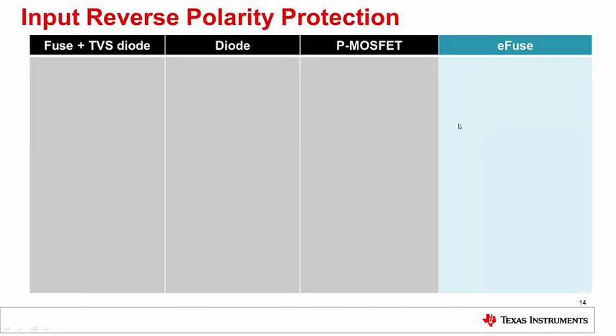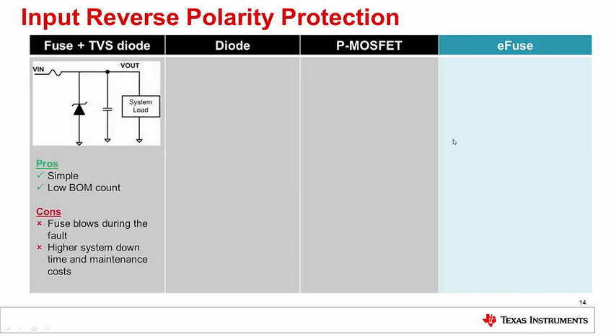Reverse polarity protection, where it is needed. In applications such as PLC systems, the input side needs reverse polarity protection against any field supply miswiring. One simple way to achieve this is by using a combination of fuse and TVS diode, where the fuse blows and protects the load against reverse polarity voltages. After the fault, the fuse needs to be replaced.